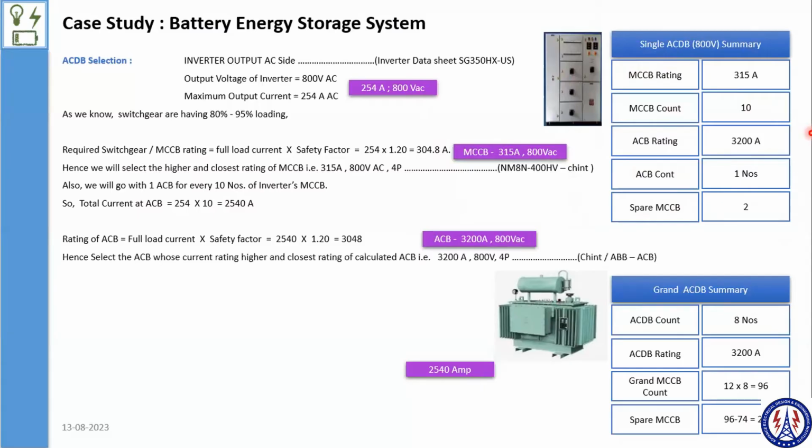Yes, we got it. Actually, one question regarding the 10 inverters: is it our choice, or is it based on the capacity of the transformer? No, it's our choice, but again, you need to find out whether you can club 24 or maybe 20 inverters in a single ACB.